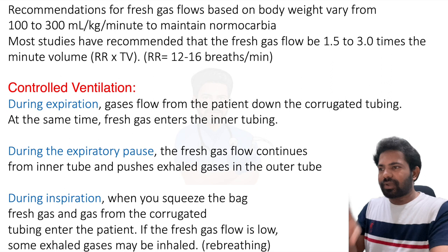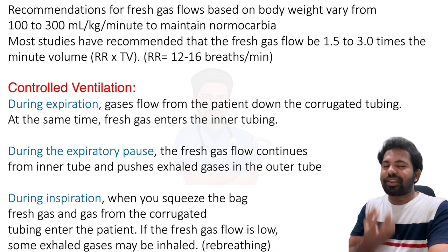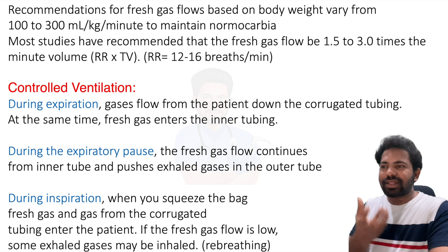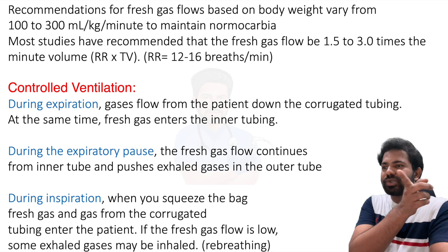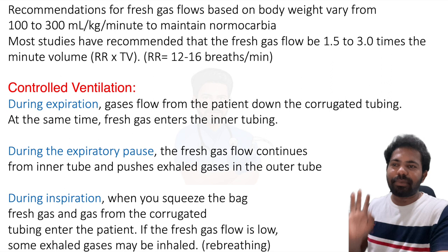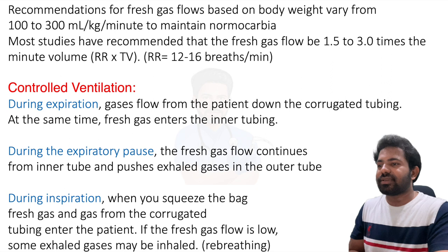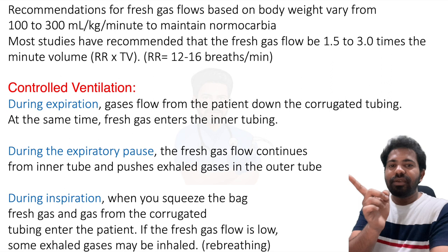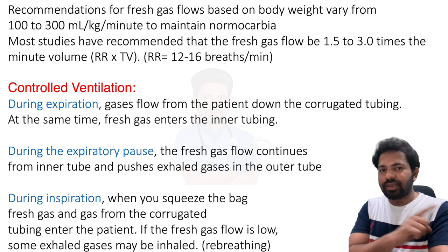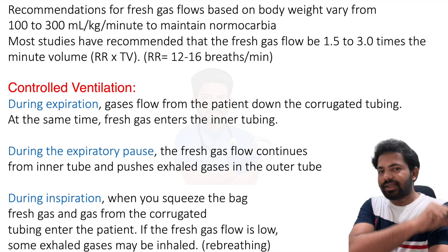After expiration there is an expiratory pause; breathing is typically 12–14 breaths per minute, so there is a pause between breaths. During this pause, fresh gas flow from the inner tube continues and pushes exhaled gases in the outer tube toward the reservoir bag and out through the APL valve. During inspiration in controlled ventilation, you squeeze the bag, and the fresh gas plus gases from the corrugated tube enter the patient — which is re-breathing. If fresh gas flow is low, some exhaled gases may be inhaled.